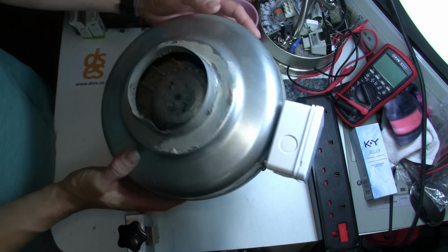The Robin sees that external voltage on its probes, and because the selector switch is still on IR, which is of course a dead test, it sounds an alarm because you wouldn't want to IR something that's live. Until the capacitor has discharged to below 20 volts, the Robin won't let me repeat this test. I'm going to do it again just to show something else.